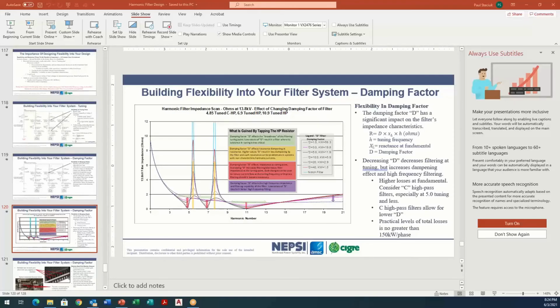So in that area we're seeing more harmonic filters, but in just about every other area that we're shipping into right now, in North America and South America, we just see standard capacitor banks. We employ a concept called filter-ready capacitor banks, which means we design a capacitor bank that can be easily converted to a harmonic filter. We call it the backup plan. The reality is, when you do harmonic studies, oftentimes it's inconclusive, especially if you're applying IEEE 519. It's inconclusive whether you will exceed the limits.